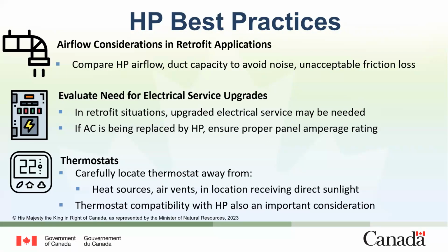In case of ducted heat pump systems in a retrofit application, it is imperative to understand the airflow capacity of the existing ducting network and how it compares to the airflow requirements of the ducted heat pumps to be installed. If the airflow of the heat pump exceeds the capacity of the ductwork, there is likely to be noise and friction loss issues that will impact performance and homeowner satisfaction.